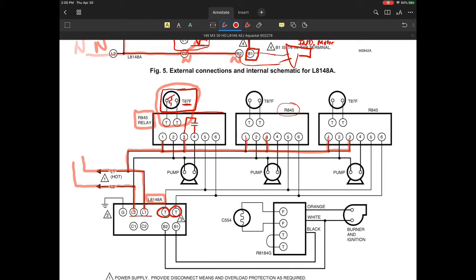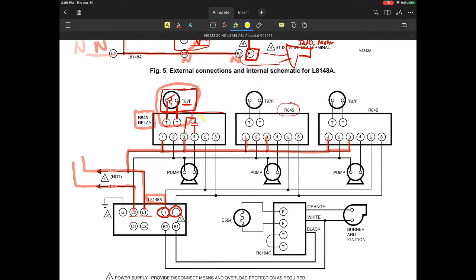So on a fall in temp of this T87F is what they're showing, but this could be any thermostat. You could do it with some sort of a battery-powered thermostat for that. Any contact closure is going to allow you to send power, and essentially you're powering up the internal relays in this system. So it's allowing you to power this relay, and they're also allowing you to power up another set of contacts in here that I'm gonna draw in here.